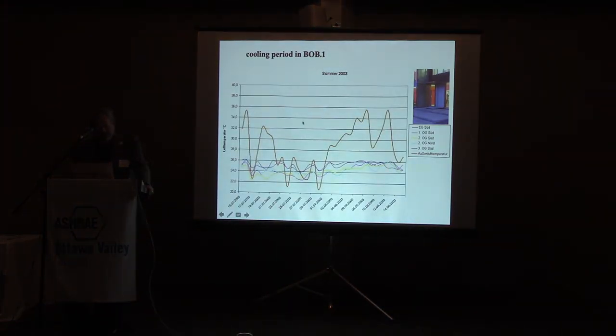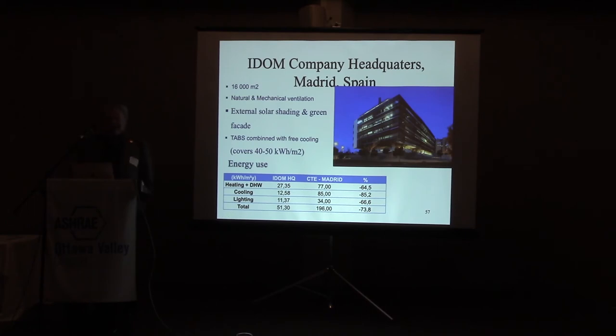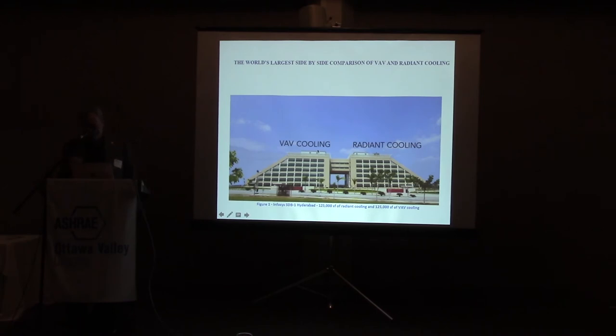Several measurements were done in the building. I'll show one here where the outside temperature during the summer went up to 30-something, and the temperatures in the different rooms are somewhere between 22 and 26 degrees. We have seen another one in Madrid. They lowered the energy use of that building more than 60% below the normal type of offices built in Madrid. But the only direct comparison of VAV and radiant is a building that has also been published in the ASHRAE Journal.